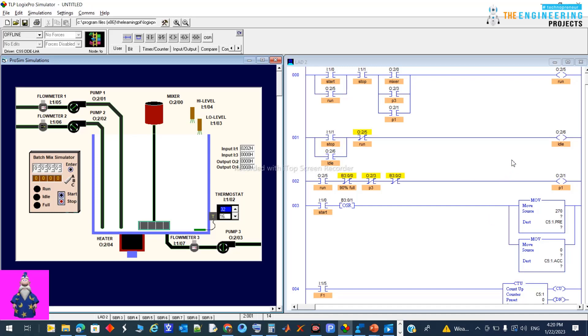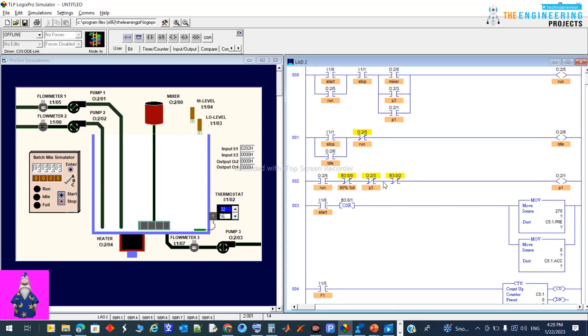If I hit stop, the run rung will deactivate — start and stop are handled here, so no additional stop contact is needed on that rung. The idle rung activates when run is not active, which is the idle or standby state.